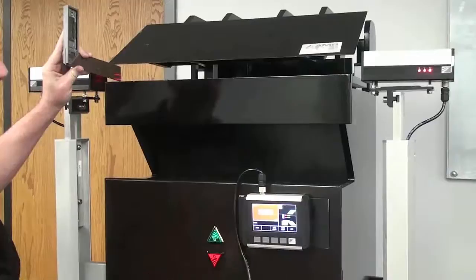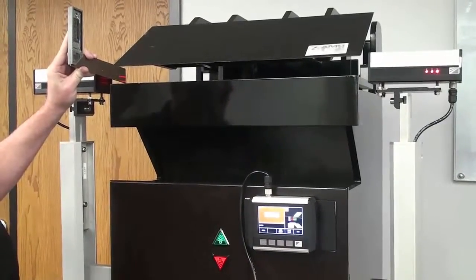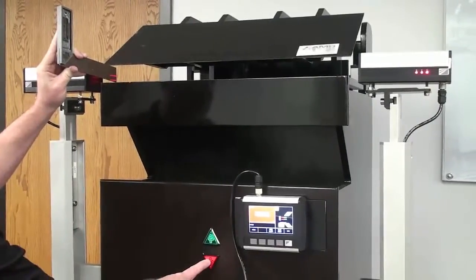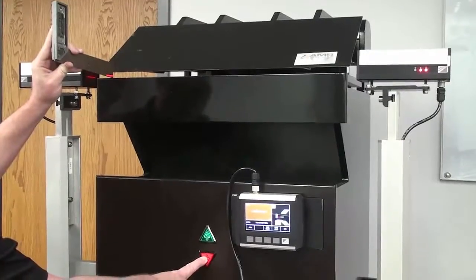I'm going to release that pedal. And I'm going to simulate that we cannot remove this obstruction. So if I do not take my fingers away or there's something else blocking the laser, when I push the foot pedal again, it's going to come down in slow. And it's going to stop at the safety stop.